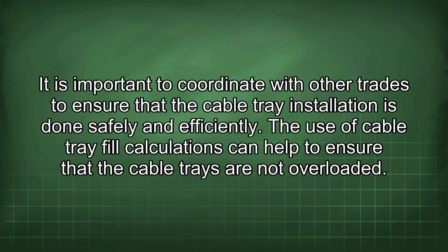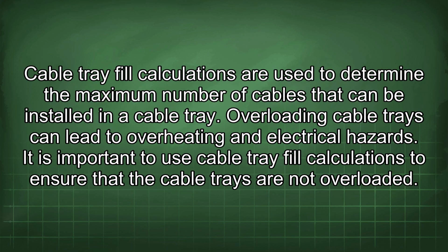The use of cable tray fill calculations can help ensure that cable trays are not overloaded. These calculations are used to determine the maximum number of cables that can be installed in a cable tray. Overloading cable trays can lead to overheating and electrical hazards, so it is important to use fill calculations to prevent this.